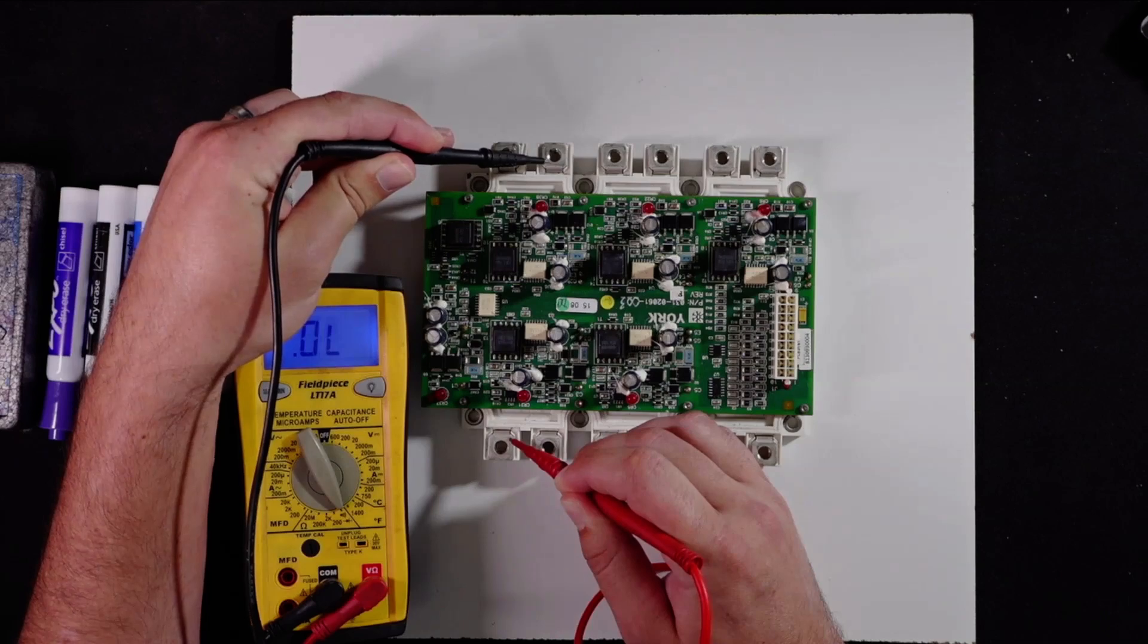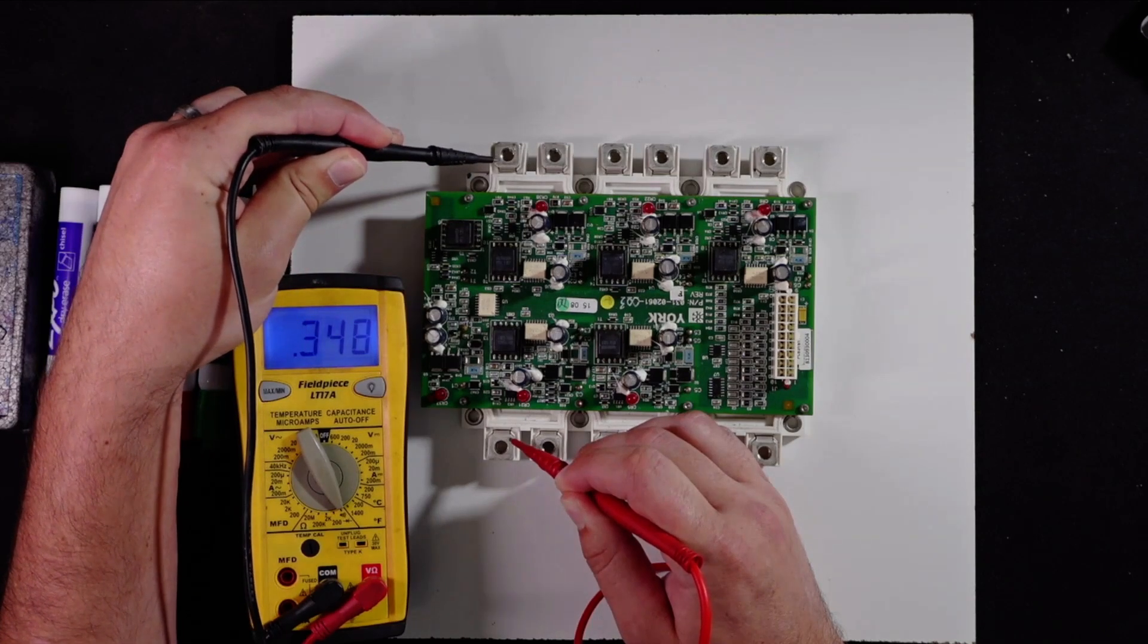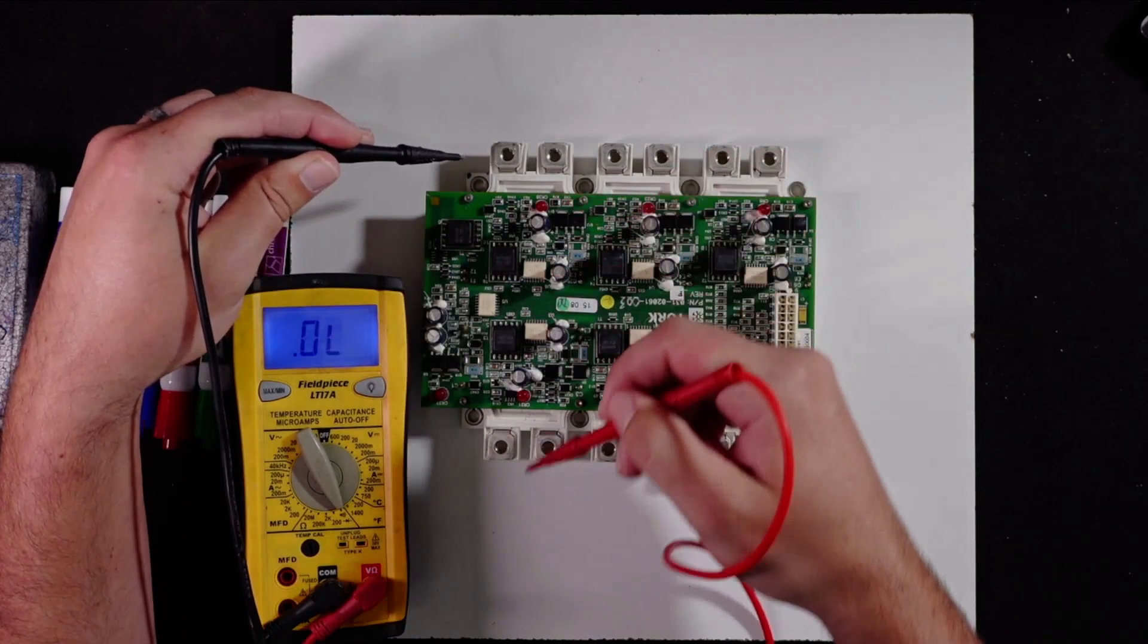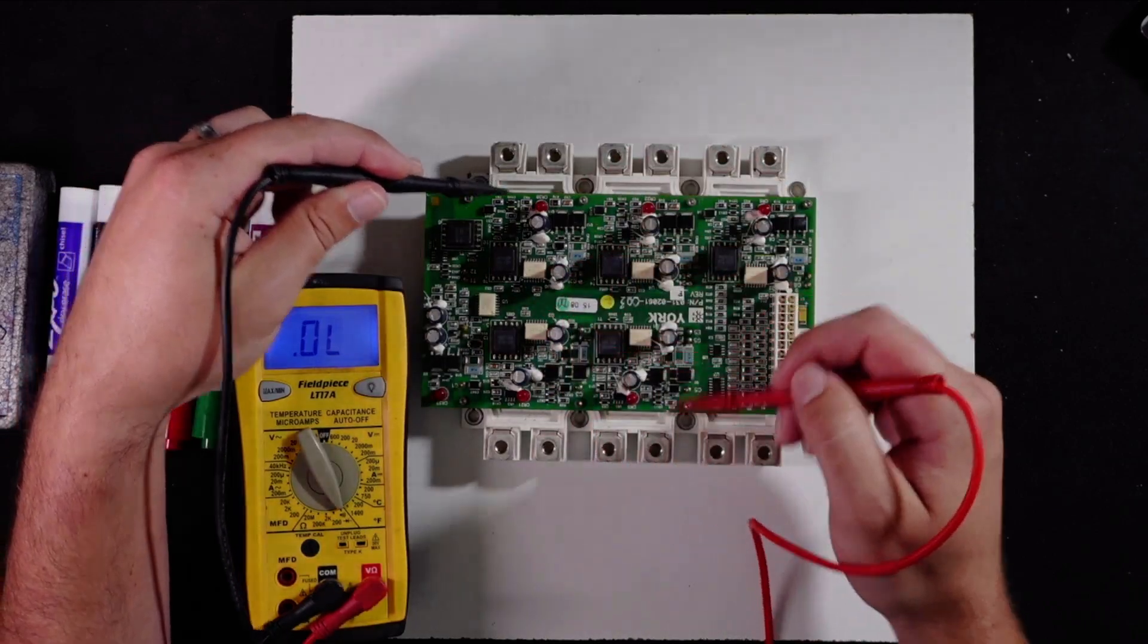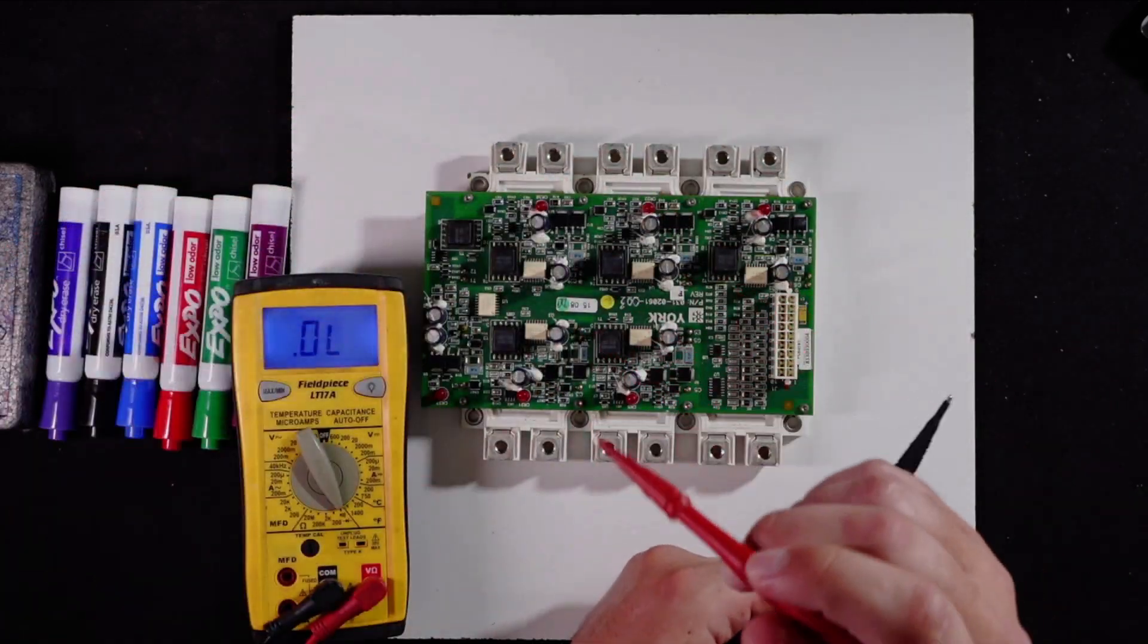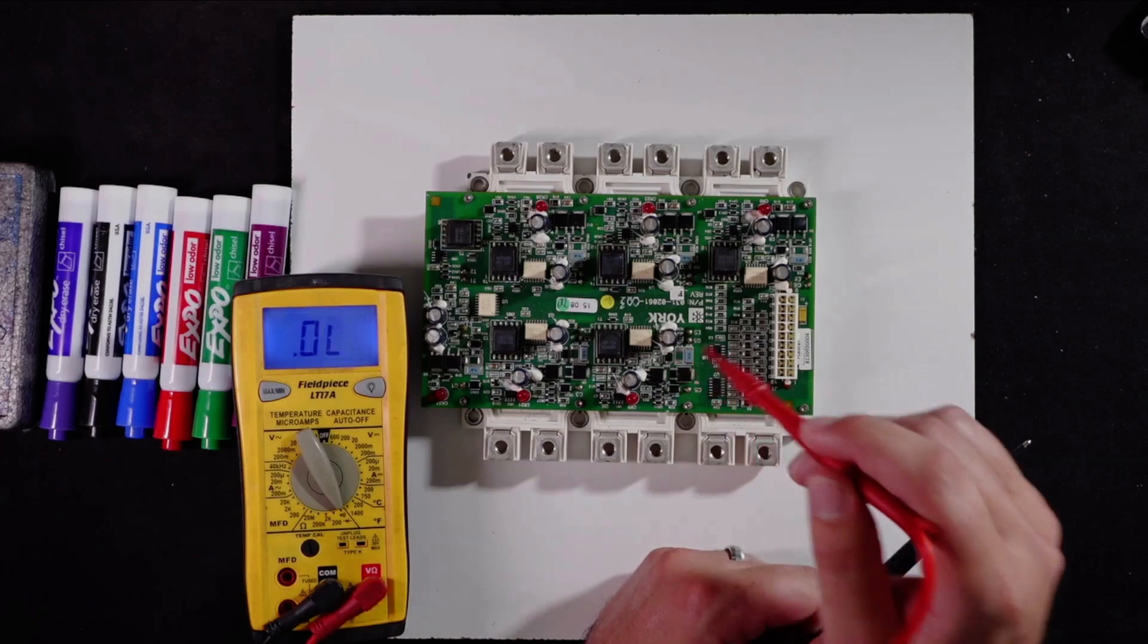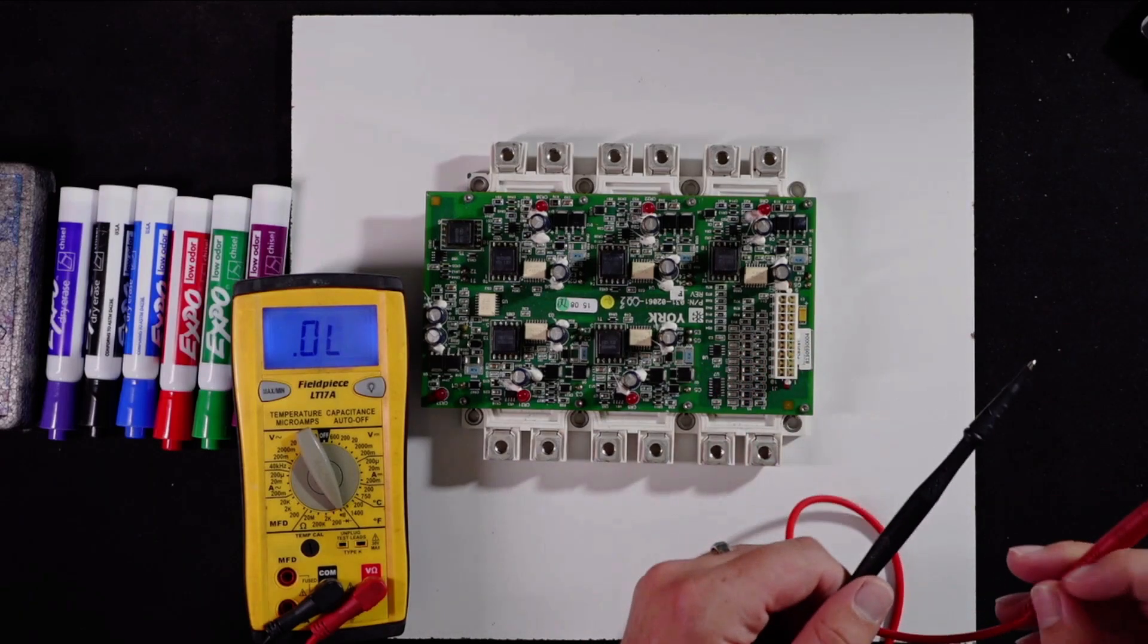So you could have a scenario where, and in the field, this test right here, this IGBT just passed. Right there, this just passed. Okay, now I could do the other three gates. But let's just say all three of these pass, but I could still be having a vibration issue from it.